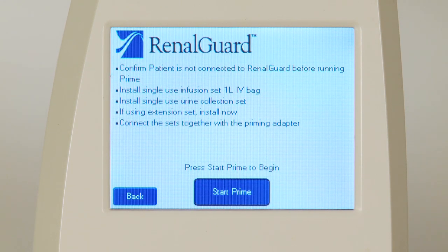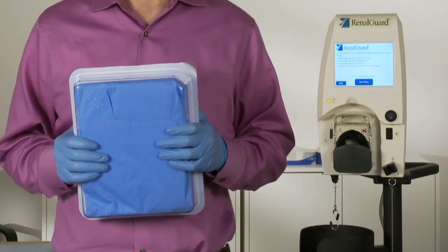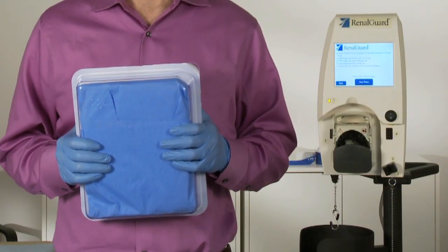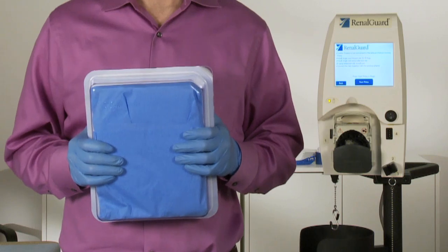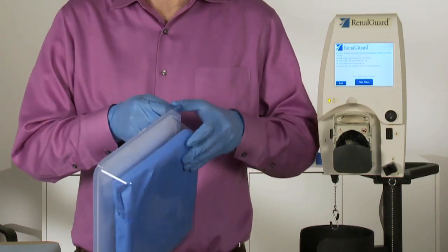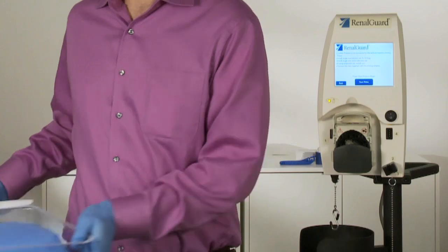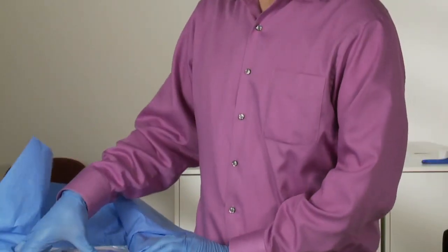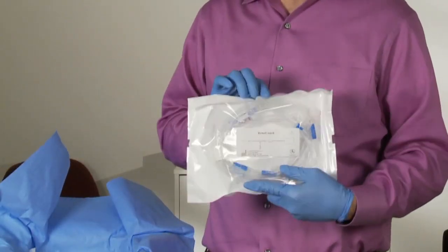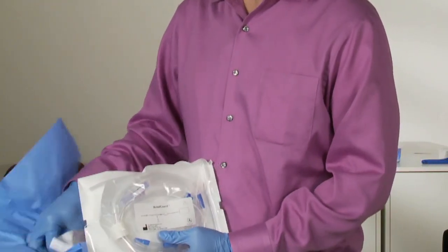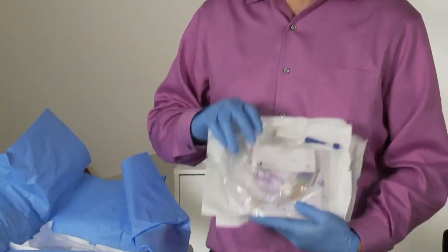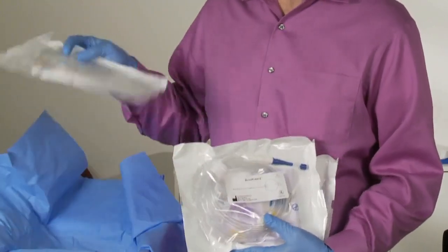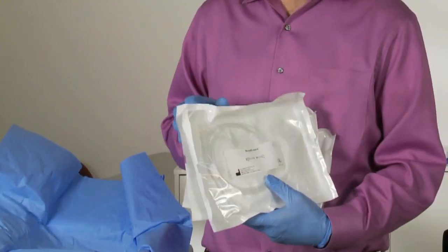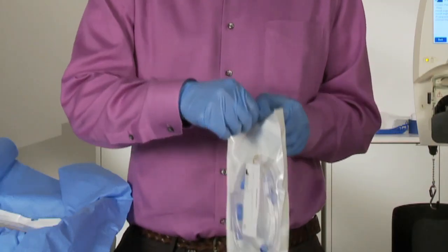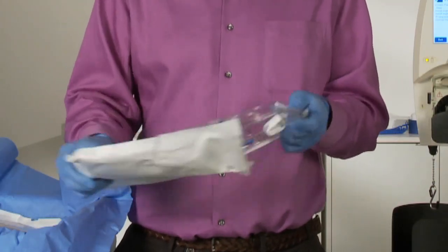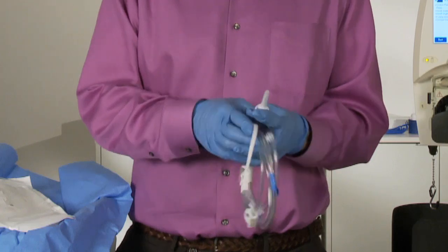Now, go ahead and open a new RenalGuard single-use set and let's load it. You're going to want a new RenalGuard single-use set and a new bag of hydration fluid. Open up the set. When you do this, it's best to be wearing gloves. When you first open the set, you'll find 3 bags: the infusion set, the urine collection set, and the collection set extension. Examine the sets to confirm that nothing was opened or damaged during shipping. Let's start with the infusion set. Take the cap off the end of the infusion set and spike the hydration bag.